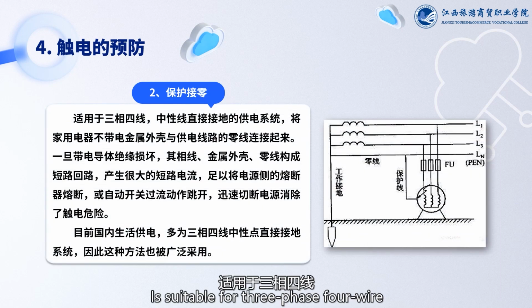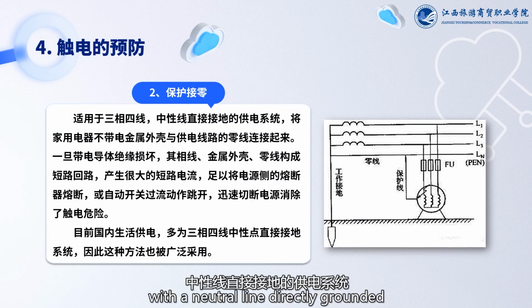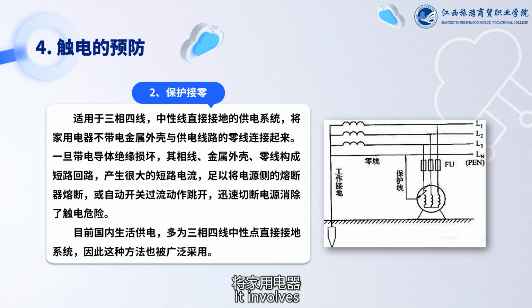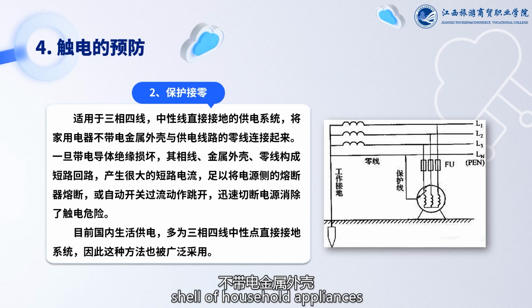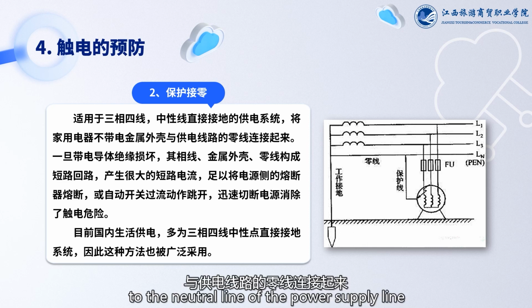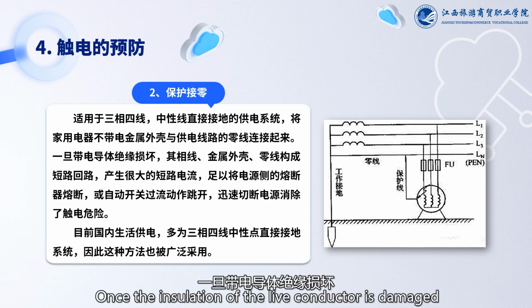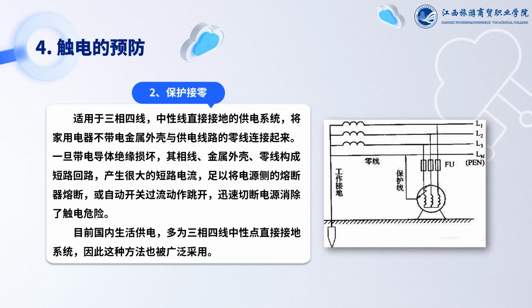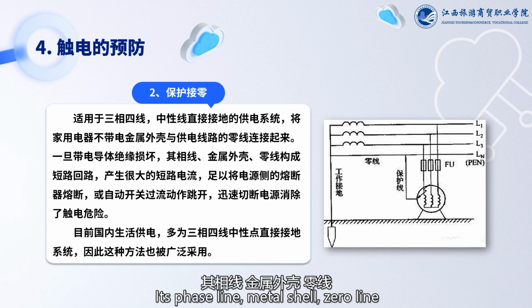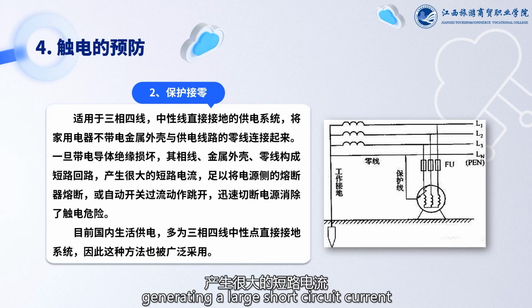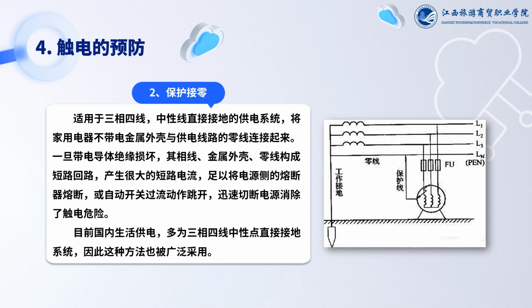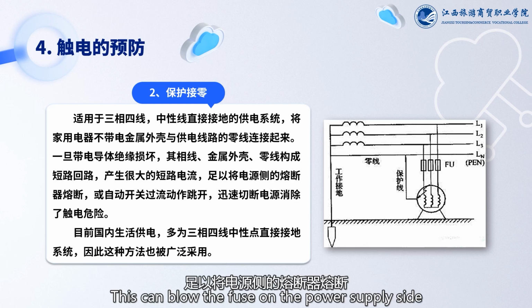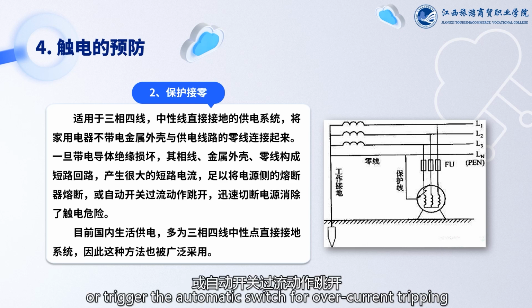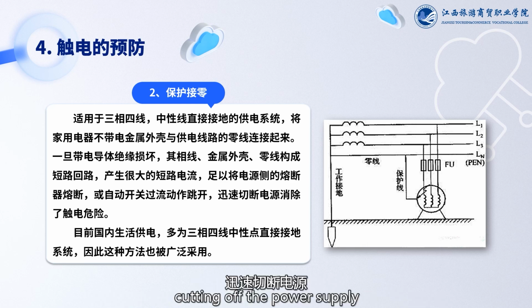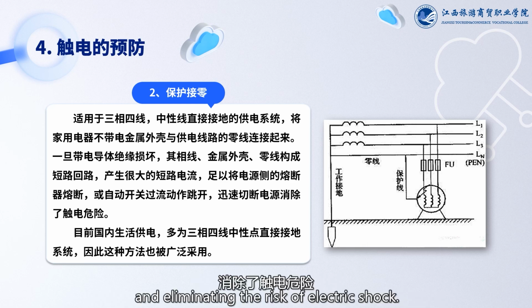Protective connect to neutral is suitable for three-phase, four-wire power supply systems with a neutral line directly grounded. It involves connecting the uncharged metal shell of household appliances to the neutral line of the power supply line. Once the insulation of the live conductor is damaged, its phase line, metal shell, and zero line will constitute a short circuit, generating a large short circuit current. This can blow the fuse on the power supply side or trigger the automatic switch for overcurrent tripping, cutting off the power supply and eliminating the risk of electric shock.